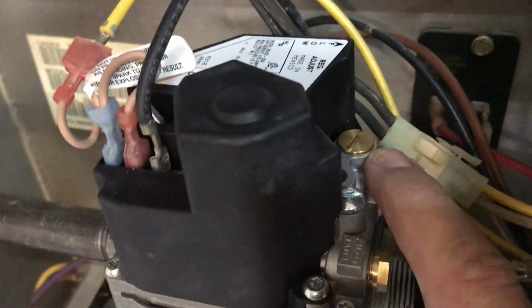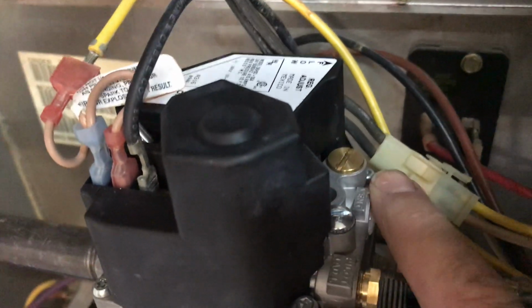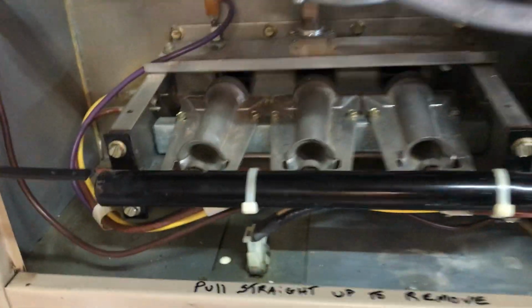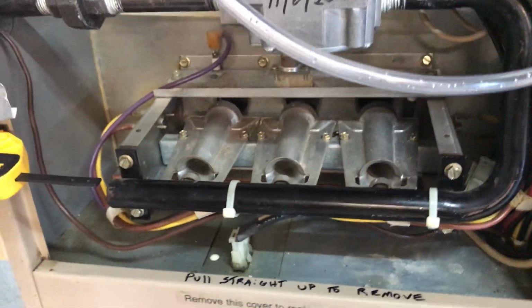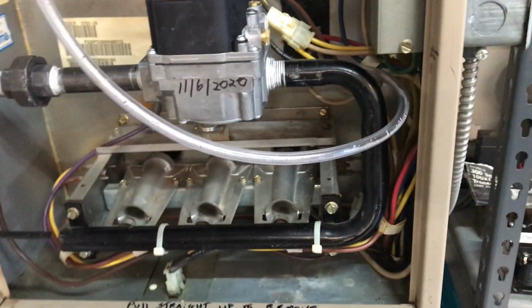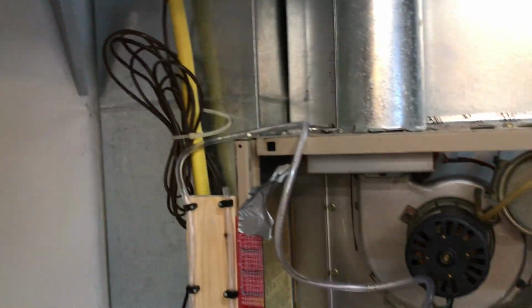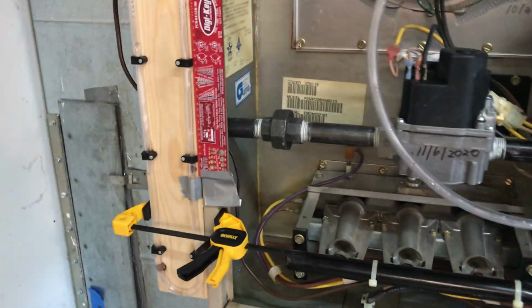So I opened up the high pressure side and took off the cover screw. There's another plastic screw in there, and I backed it off exactly 1/2 turn. And it seemed to work. It lowered the flame just a tad, and it never overheated all night long and all day today. But when I did that, I didn't have a homemade manometer, so I don't know what water column pressure I actually had. It's in the manual, what the range is.